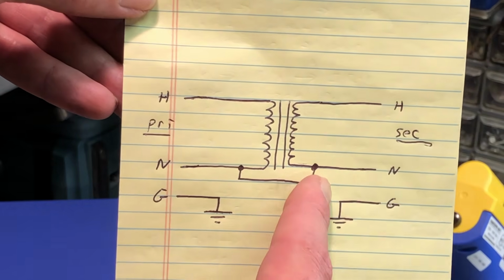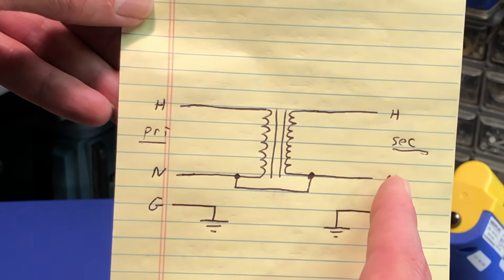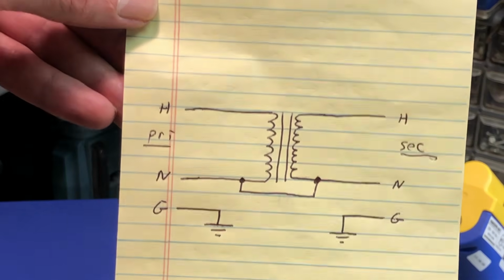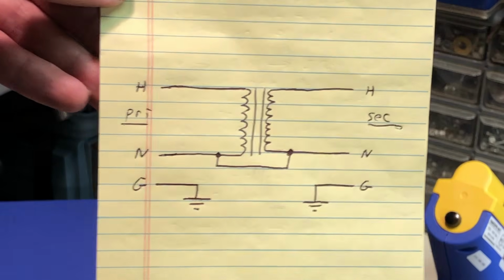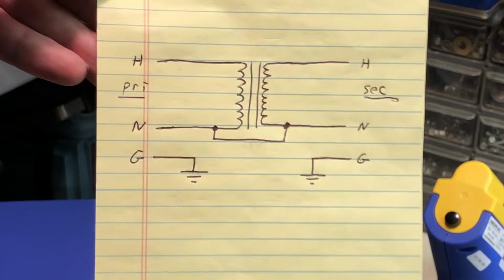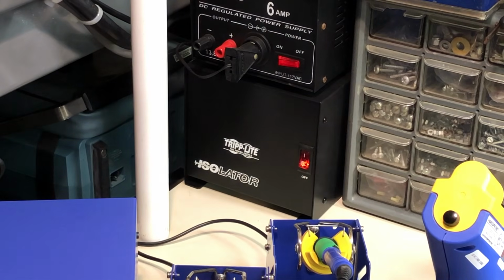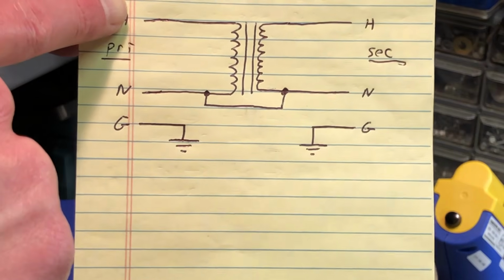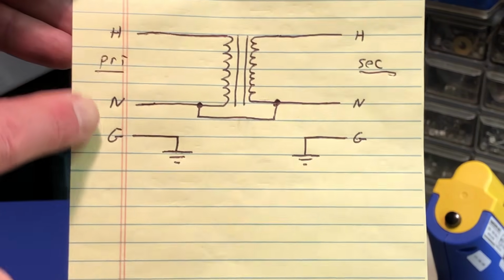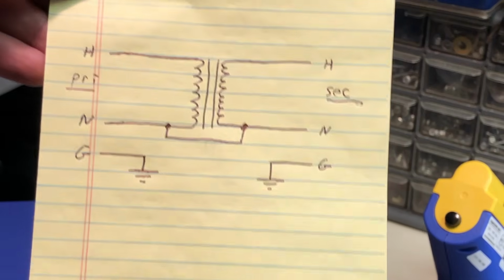You need complete electrical isolation from one side to the other. And this link again needs to be removed so that the hot and neutral over here have no reference to anything in the outside world, so to speak. You don't want any reference to a ground connection. All right? So if you pick up one of these isolation transformers, a Tripp Lite, there may be others out in the market as well, but it's always a good idea to look at the design internally and see if there's any connection like that between primary and secondary. You can do a quick test with an ohm meter and basically verify that. If you take an ohm meter and connect from any of the connections on the AC input on the primary, you should have no continuity whatsoever to the secondary.